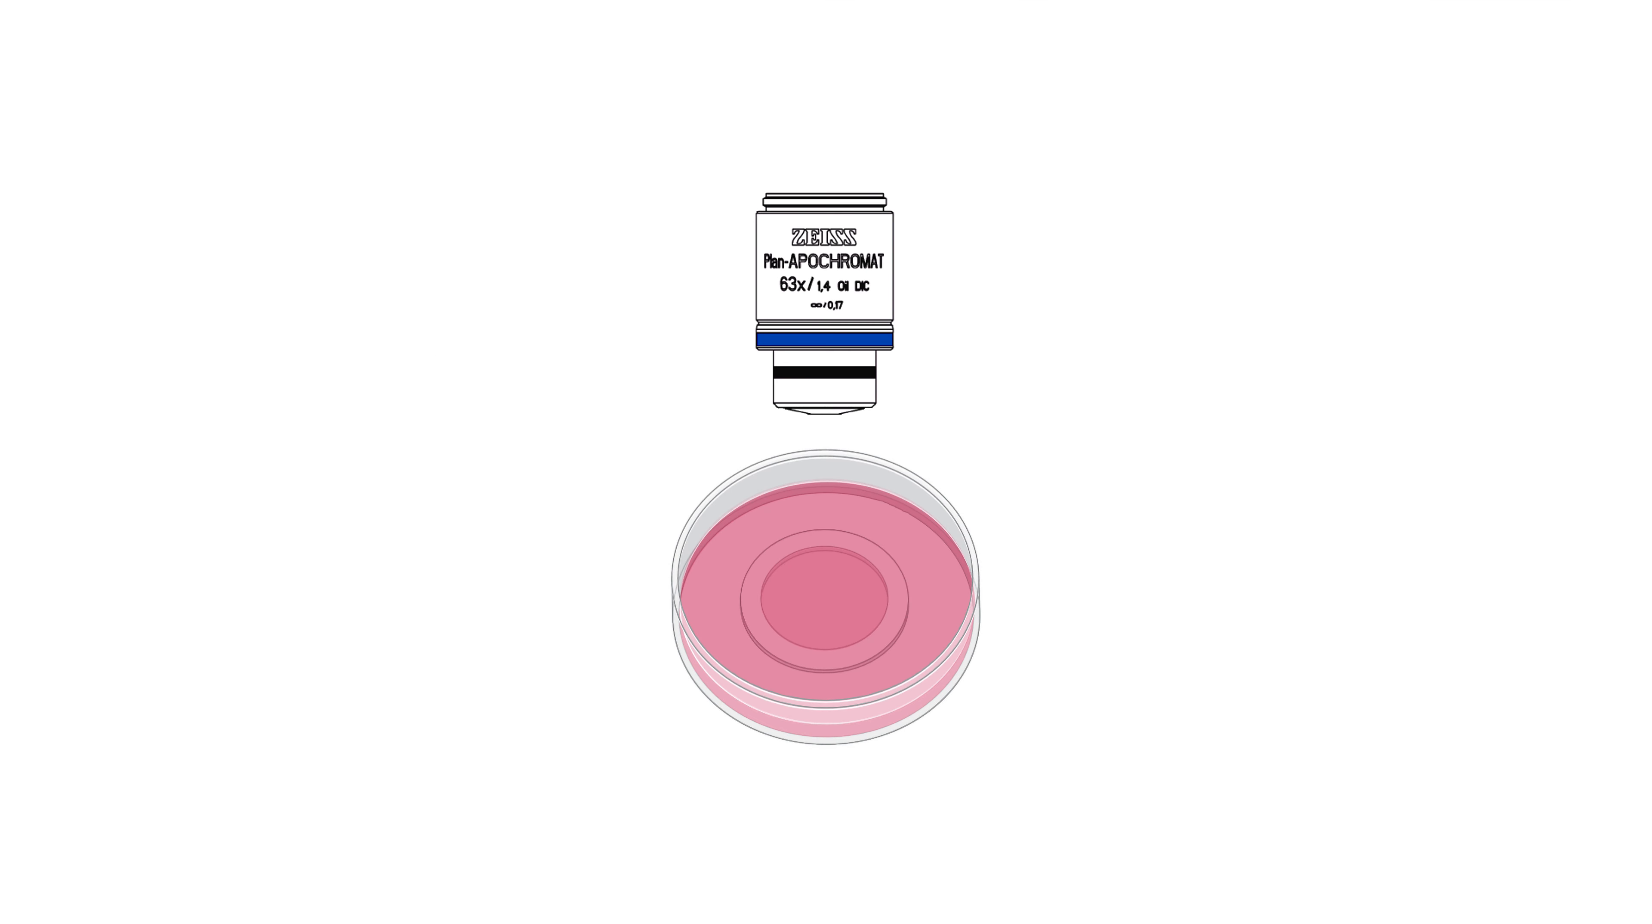You might be tempted to use an oil immersion objective with a specimen mounted in an aqueous solution. The oil lenses have a higher NA, so they should give you better resolution, right? Remember that the theoretical resolution calculations assume that the refractive index of the immersion fluid matches the refractive index of the specimen.